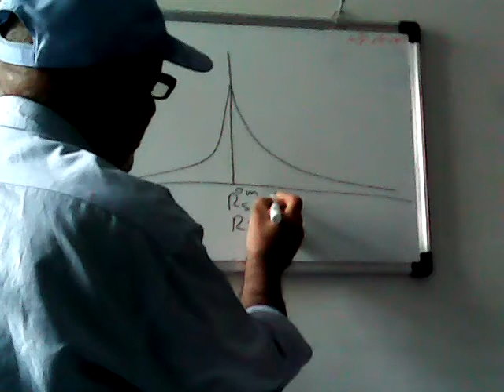Zero meter, 120 volt. Step 1 meter over here. At 1 meter, we have a step voltage of 81. At 2 meter, 51 step voltage. At 5 meter, 25. At 10 meter, 8. At 20 meter, 0.